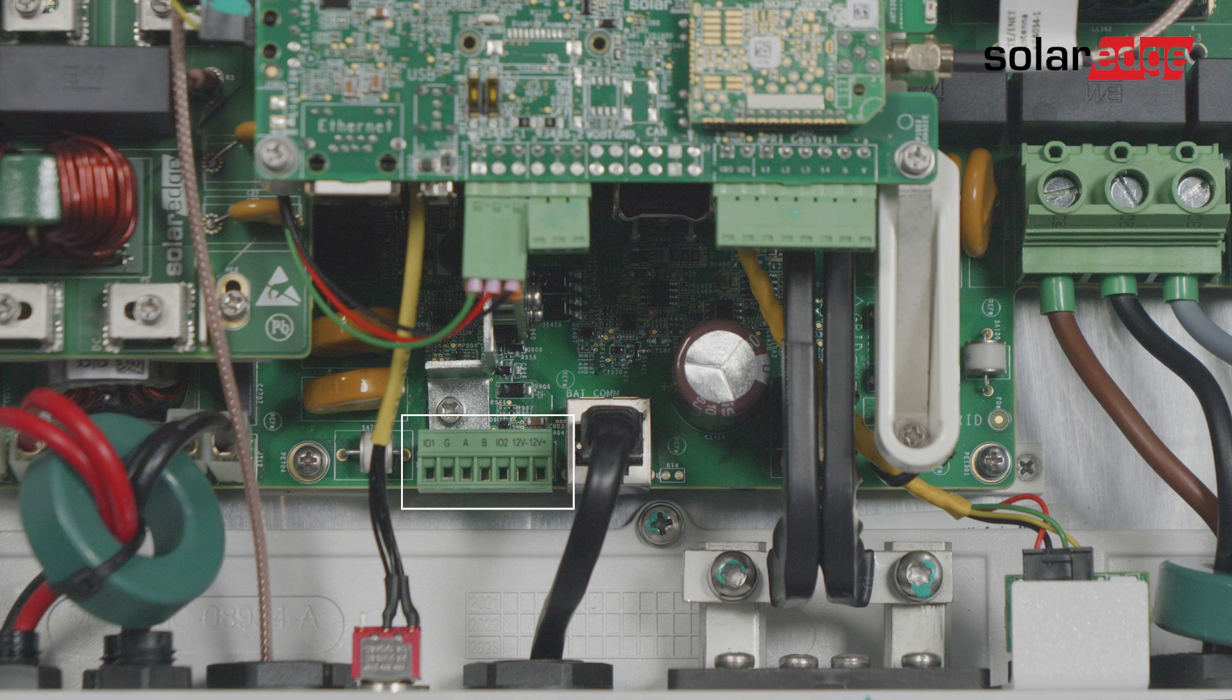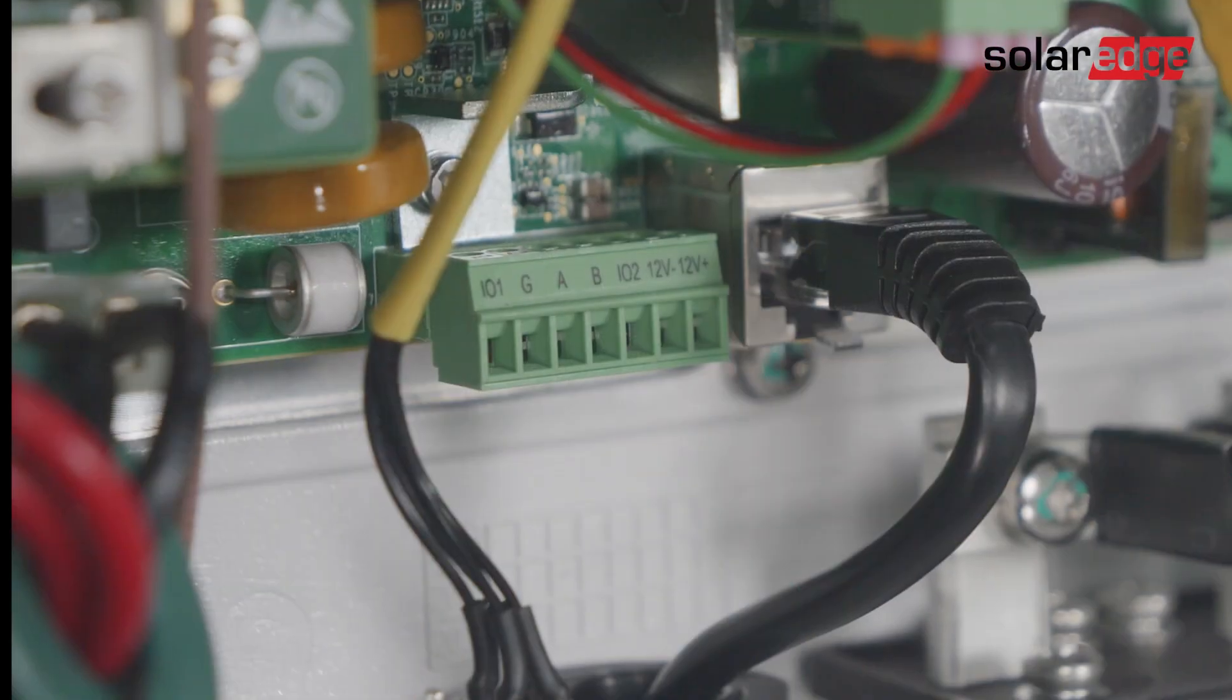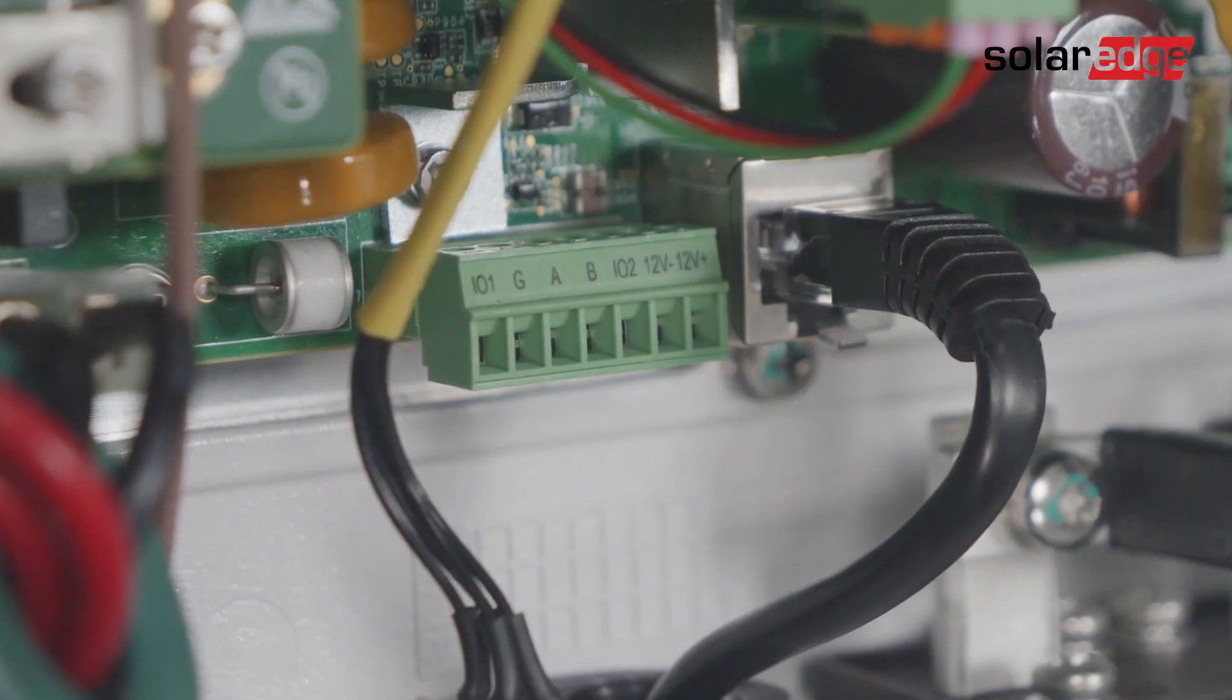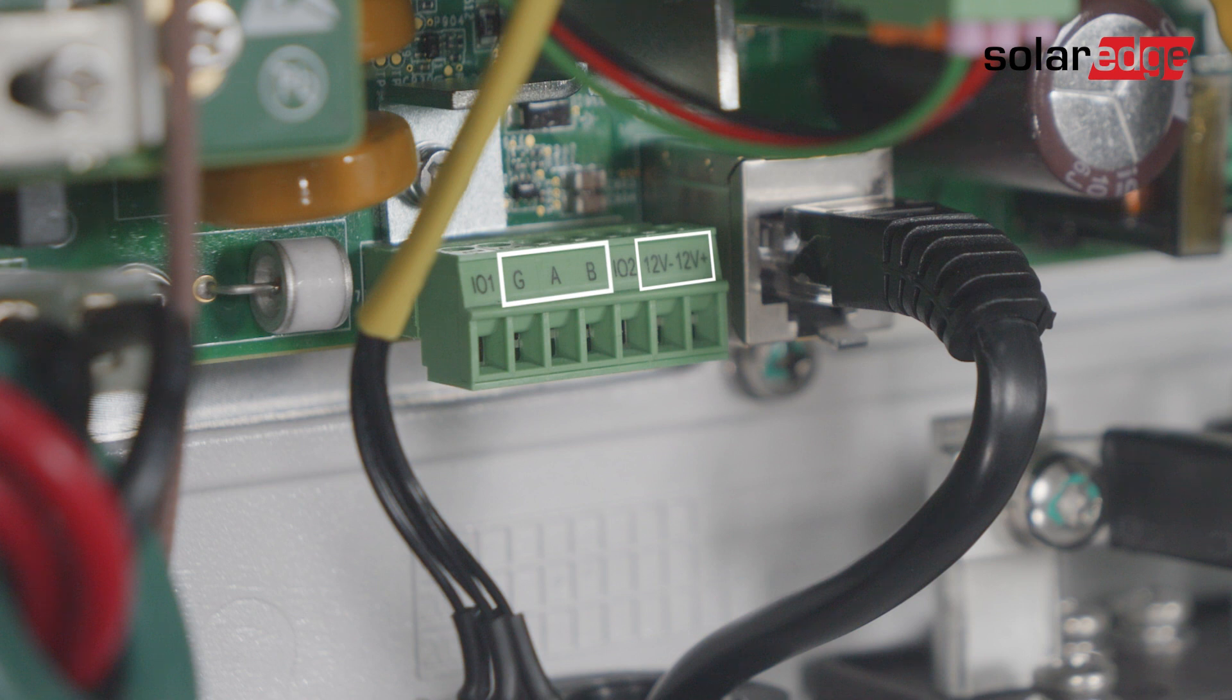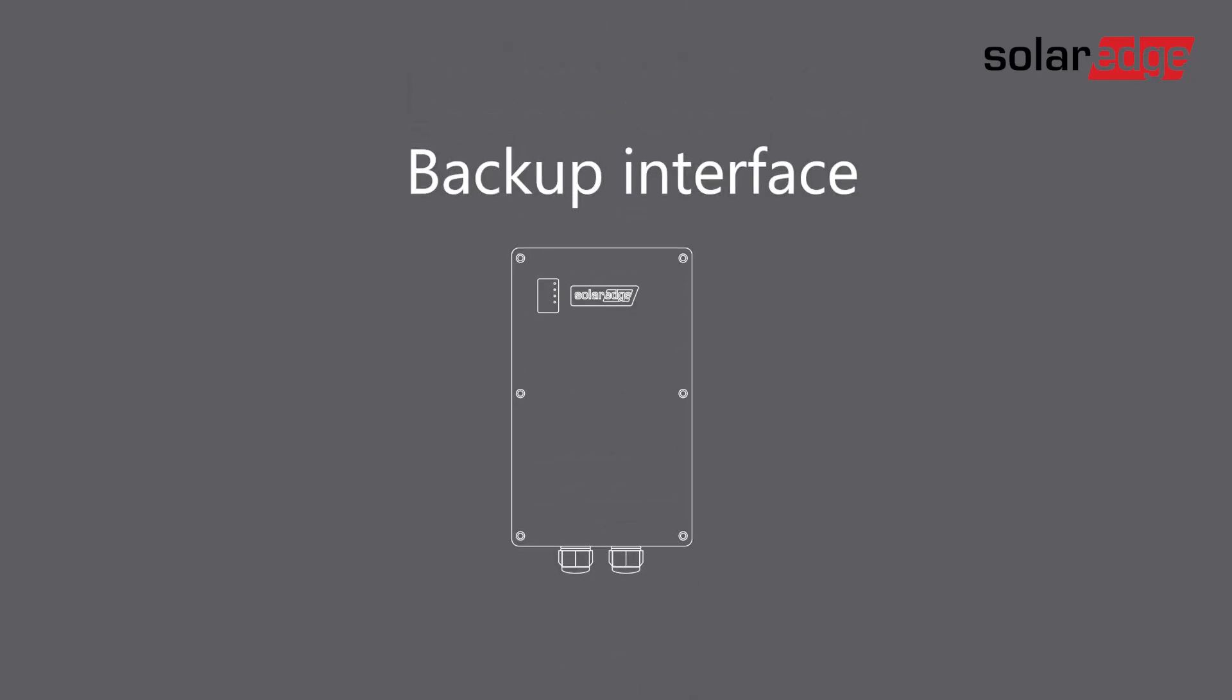This 7-pin connector is used to connect the backup interface or the energy meter. In case you have a backup interface, use a 5-wire cable to connect it to the inverter in the following scheme. If you don't have a backup interface in your system, use a 3-wire cable to connect the meter to the same connector in the following scheme. For both options, SolarEdge recommends using a CAT-5 cable. In this video, we will show the backup interface connection.